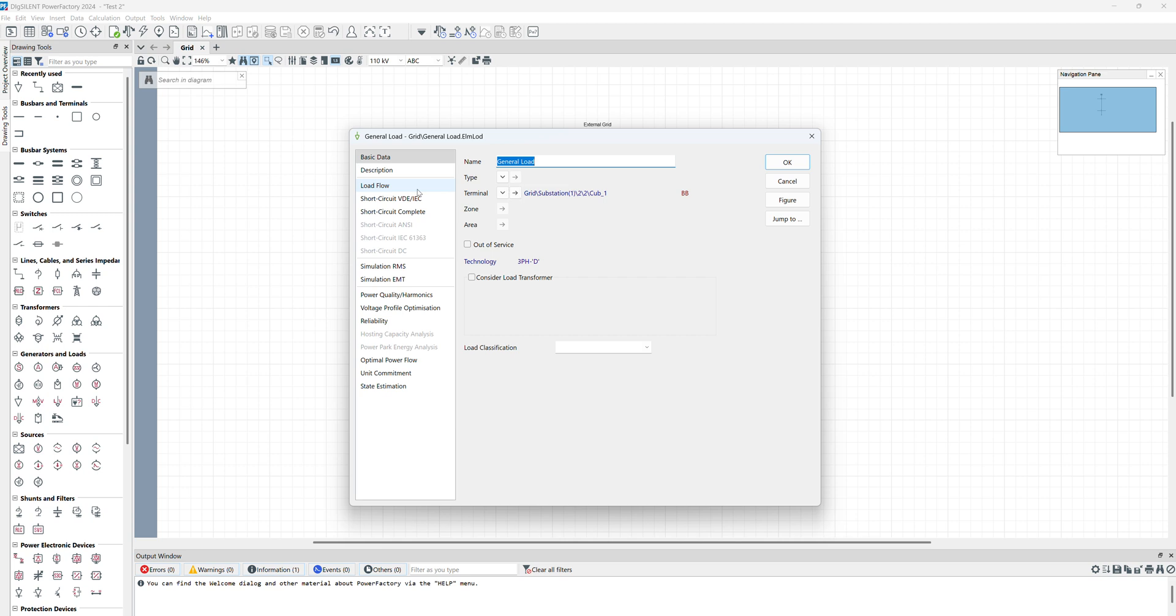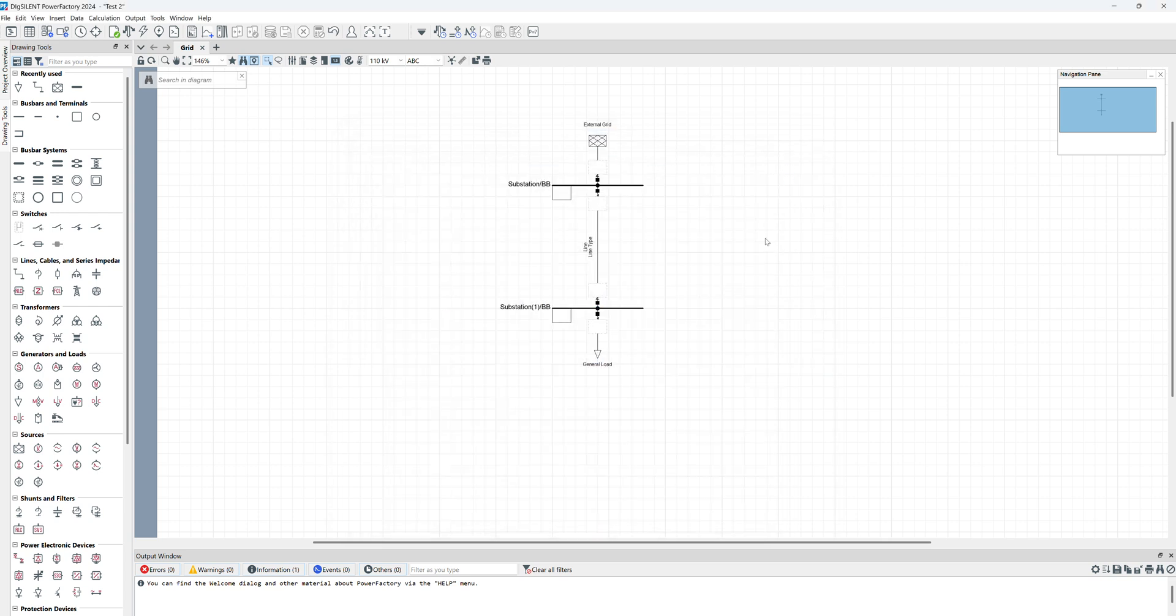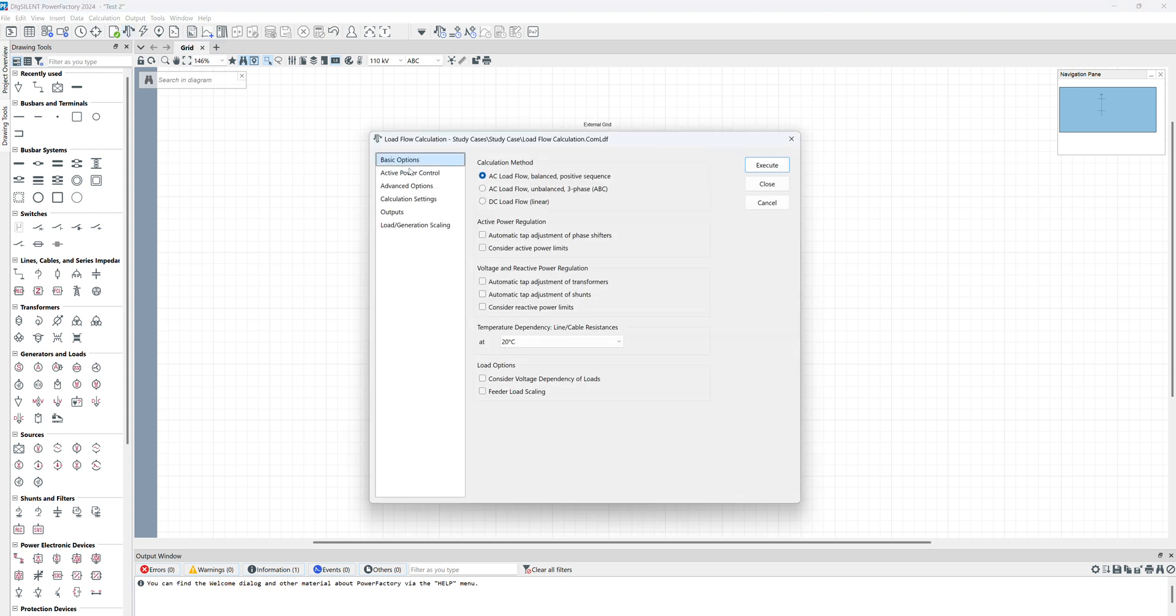If we click OK, the next component is this general load. It's not necessary to allocate any types, but we should allocate amounts of the active and reactive power consumption. If you click on the load flow, in the active power we can put, for example, 0.1 megawatts and 0.1 megavar. Click OK. Now we have a model. If we want to apply load flow on this model, for doing that in top we have Calculate Load Flow or Control plus F10. If you click on that...